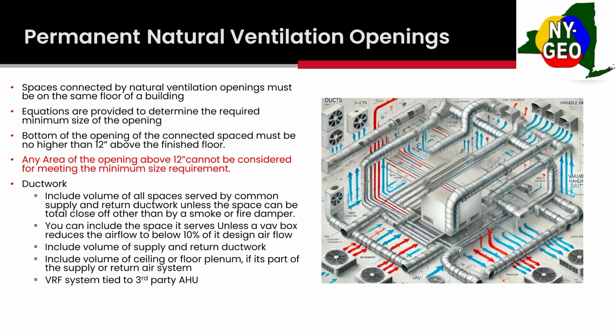So, natural ventilation. I know there's a lot of words on this, but there's a lot to go over here. Previous versions of ASHRAE 15 left it up to the design engineer to decide what is natural ventilation and how big to make the louvers. Now the new version of ASHRAE 15 sets specific requirements for those natural ventilation openings. They provide equations to size those louvers. And I think the big thing is the bottom of the opening has to be no higher than 12 inches above the floor. Previously, if you're doing a rooftop system, you might put a transfer grill above a door. That's not going to fly anymore. You would have to put it pretty much at the bottom of the wall, because refrigerant is heavier than air, so it's going to collect at the bottom of the floor. So you want to put those natural ventilation louvers or grills where the refrigerant's going to collect.